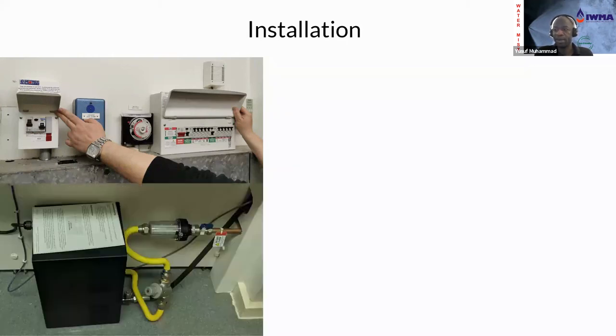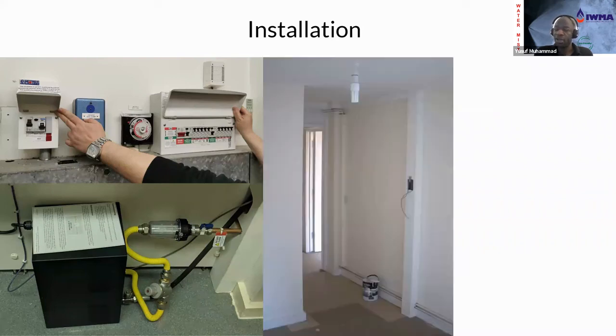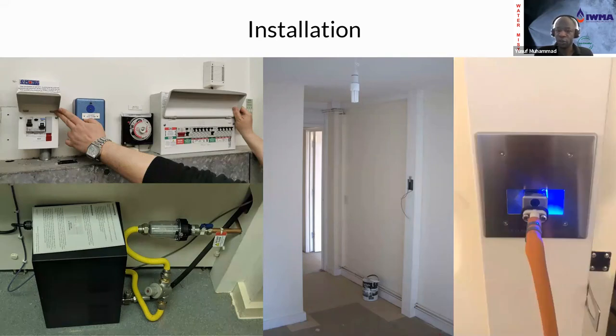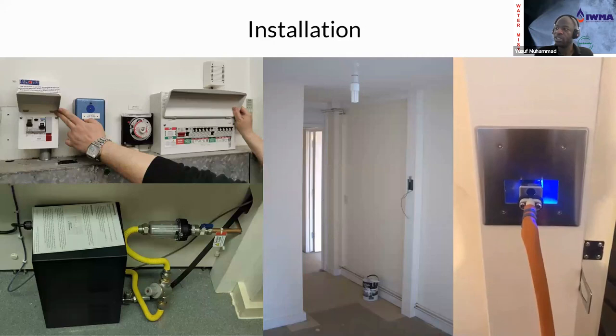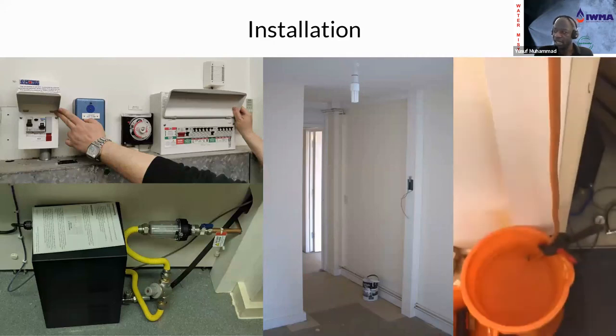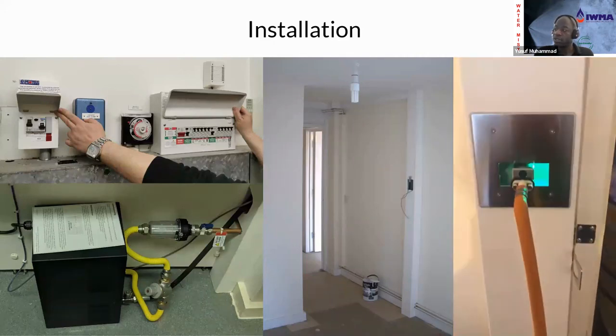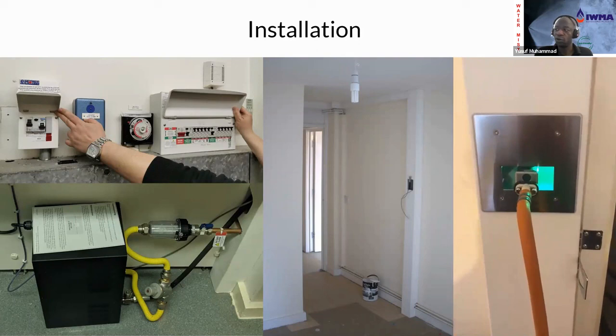You've got your pump connected to the mains water with your filter there, your check valve. And from there, you can either run your hoses within the wall, so behind that fire barrier there, or within fireproof trunking, and then you have your individual heads. We have a commissioning procedure where we test the flow on each one of those individual heads, as it's the only way you can be confident that the system will perform when called upon.